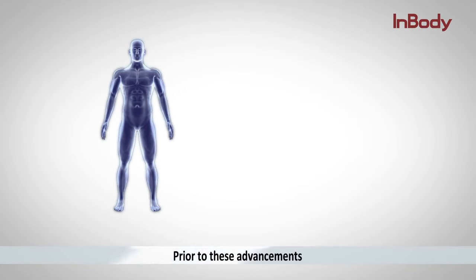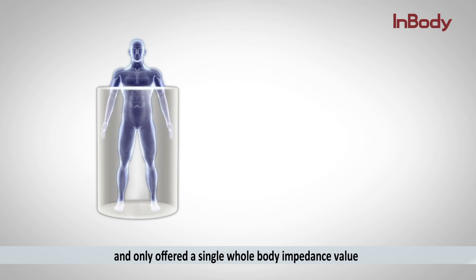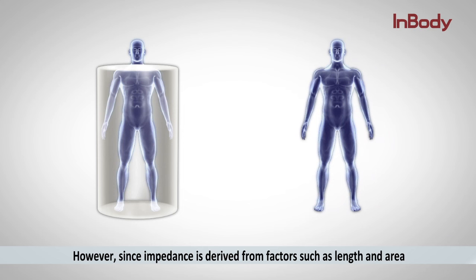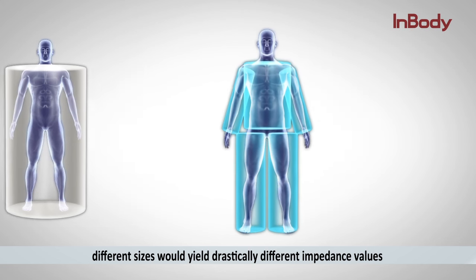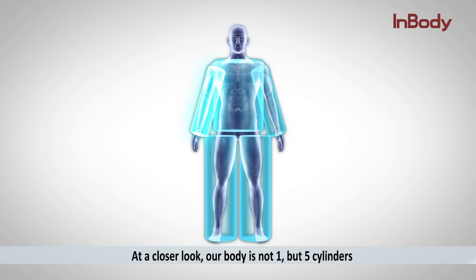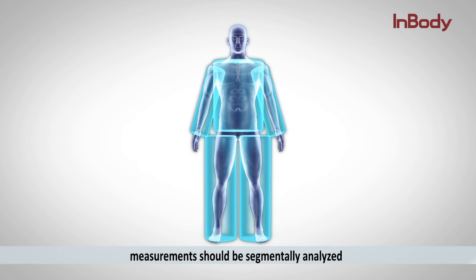Prior to these advancements, the conventional BIA method considered the human body as one cylinder and only offered a single whole body impedance value. However, since impedance is derived from factors such as length and area, different sizes yield drastically different impedance values. At a closer look, our body is not one but five cylinders with different lengths and widths, and therefore measurements should be segmentally analyzed.